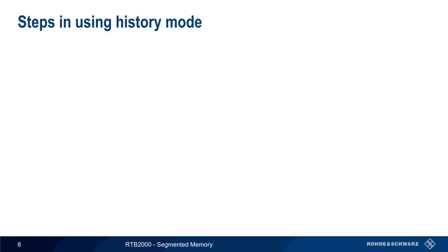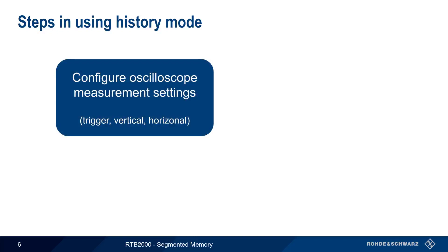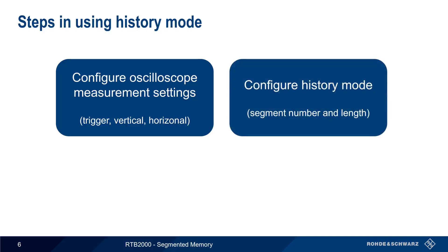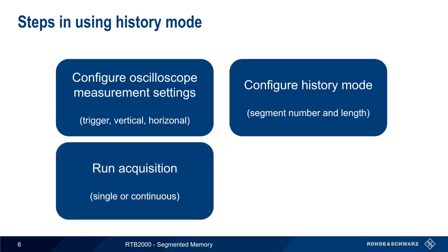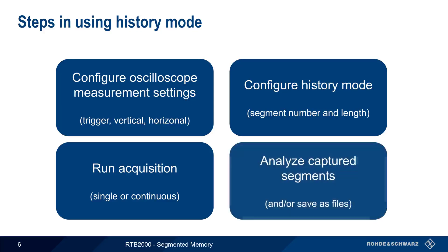On the RTB2000, segmented memory configuration and analysis are called history mode, and there are four main steps in using history mode and segmented memory. First, we need appropriate measurement settings for the trigger, vertical, and horizontal systems, which are usually the same as the settings you would use if operating with non-segmented memory. Second, the history mode parameters have to be specified: the number of segments to capture and the length of each segment. Next, we run an acquisition, which can be made in either a single shot or a continuous mode. After acquisition has been stopped, the captured segments can be viewed, analyzed, and/or saved as files.